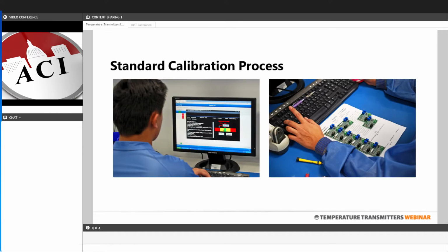I wanted to talk for a minute about our calibration process. We use a proprietary calibration software system to calibrate all of our temperature transmitters, whether or not they're NIST certified. This delivers a higher level of accuracy and consistency than calibration by hand using multimeters can provide. As a result of this process, our temp transmitters are not able to be calibrated or recalibrated in the field, and that's a good thing. There's no mechanism for these to be calibrated in the field, either advertently or inadvertently, so there's no way that these sensors can be thrown off or knocked out of calibration in the field.